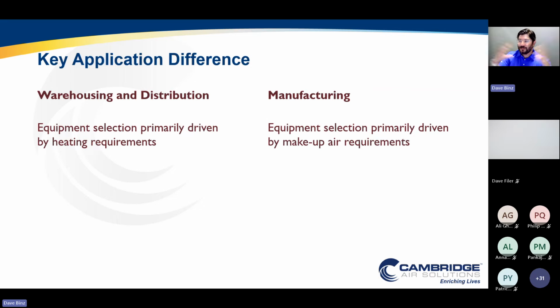So with that, the building's the same, the structure's the same. Most of these buildings may actually have the exact same construction, walls, insulation, and type. However, now when I look at the HVAC system, I've got to solve my ventilation first. In the warehouse, I'm typically driving my heating and ventilation solutions primarily on heat-driven requirements because I have low ventilation requirements. And on the manufacturing side, it's the opposite. I have low heating requirements because of maybe internal heat gain or other challenges, but this highly variable ventilation requirement pushes me into more of a ventilation-driven solution. And so we're going to talk today about those differences, how they impact the HVAC solutions that we might recommend, or how we might combine the two, as many of these facilities have almost a combination of both spaces, maybe even in the same facility.